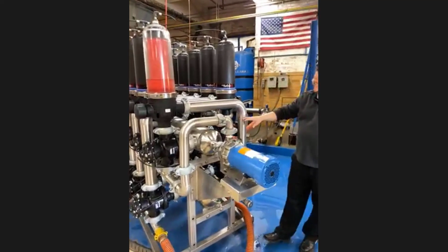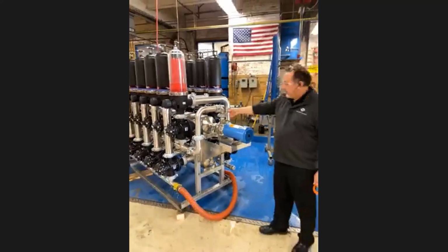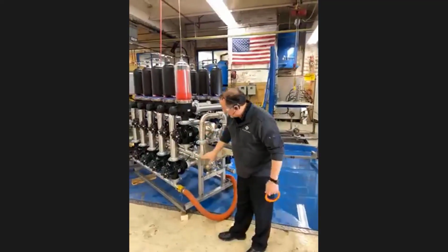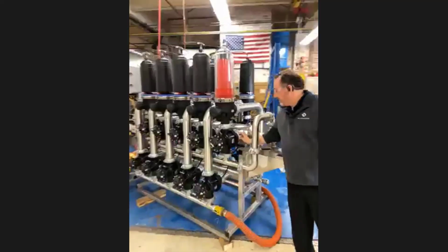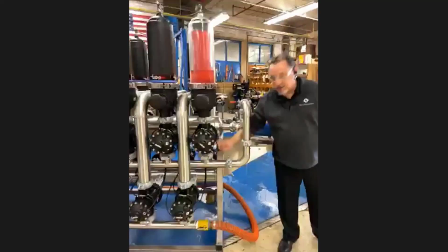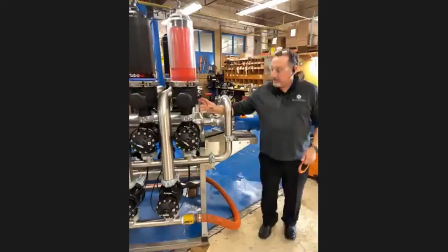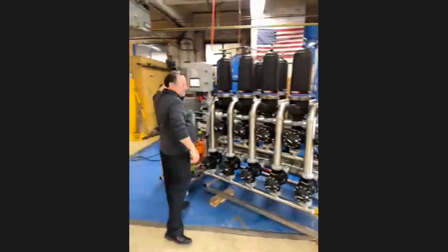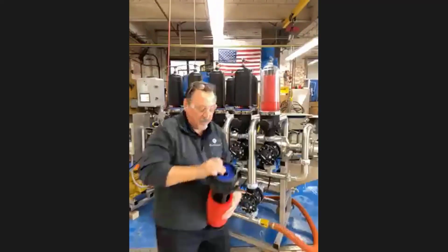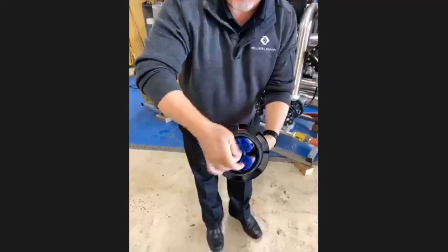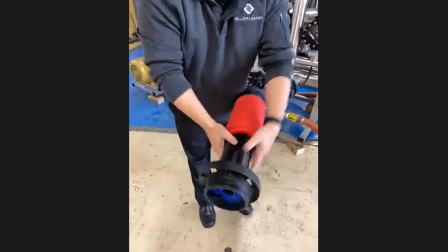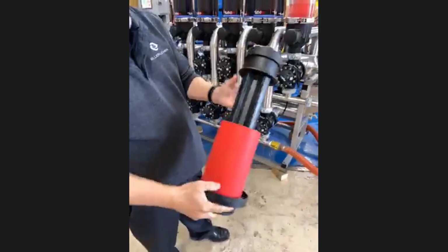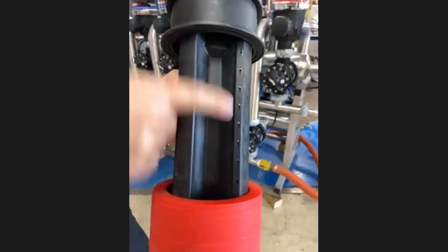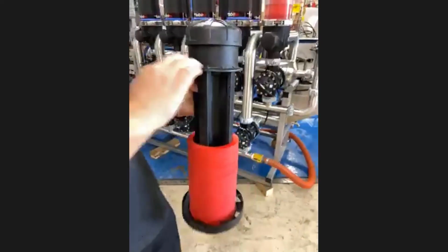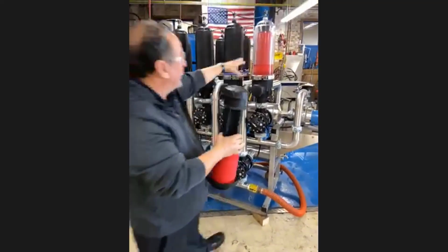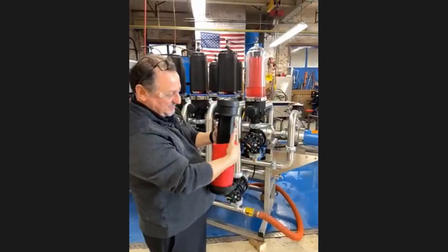During the backflush process, what happens is that we take clean water off the clean water manifold right here, send it through a booster manifold right down through here. Of course, this would now be open. So what it does is it shuts. It's open straight across now, not at an L. Comes through the unit from the bottom. As it enters the unit from the bottom, it closes the check valve right here. Remember, it's open during filtration, closes it, travels up the spine, shoots out of the 120 jets, which are located on the spines right here. I don't know if you can get that, but each spine has jets on it, which then scour and clean the disc. Also, this decompresses, so it's compressed as it is right now, and it decompresses the disc to separate the disc, to spin and clean the disc.